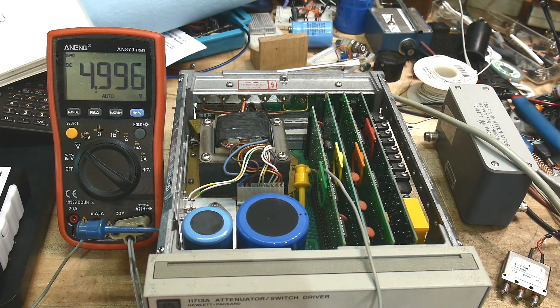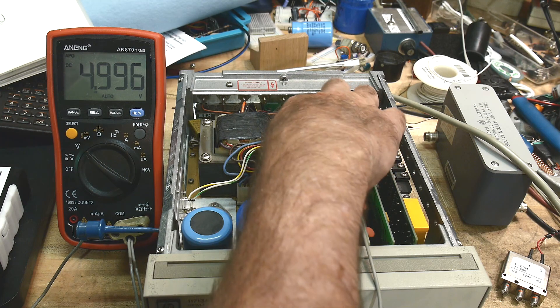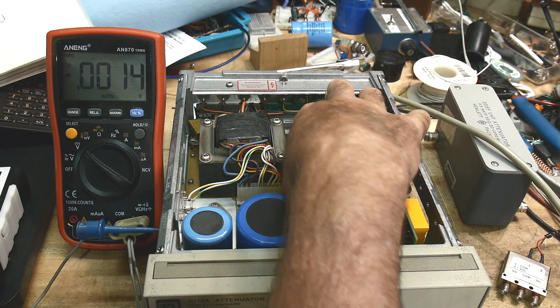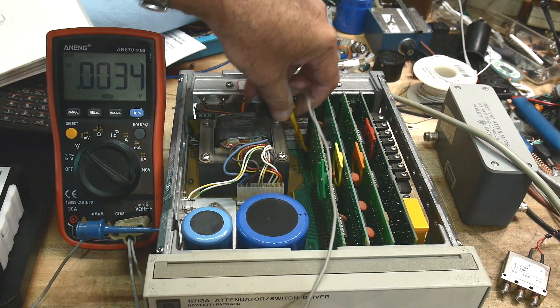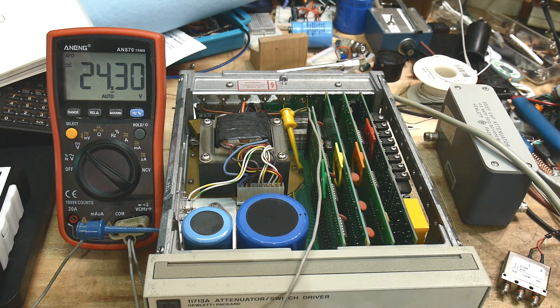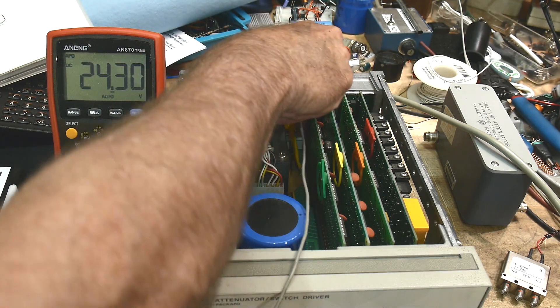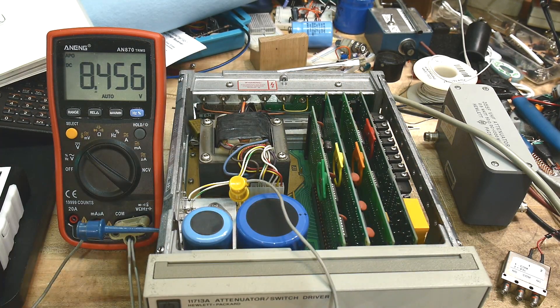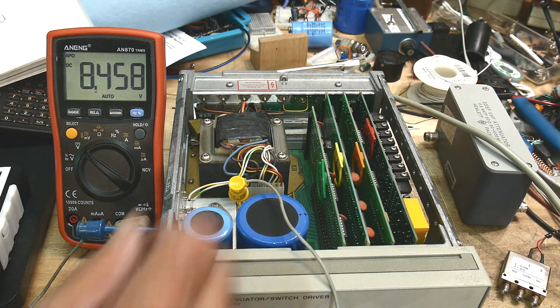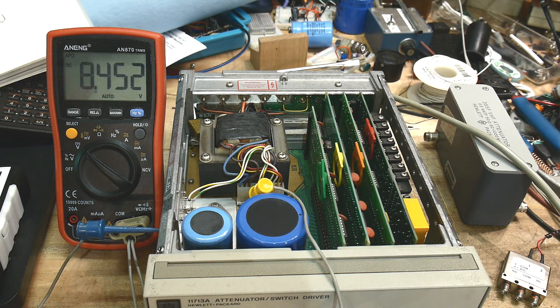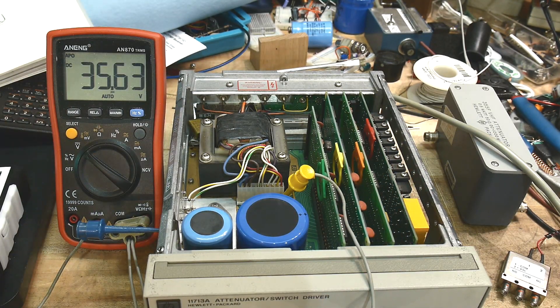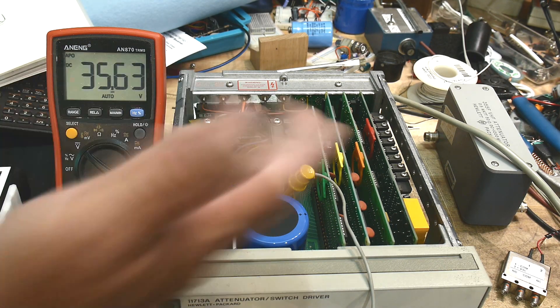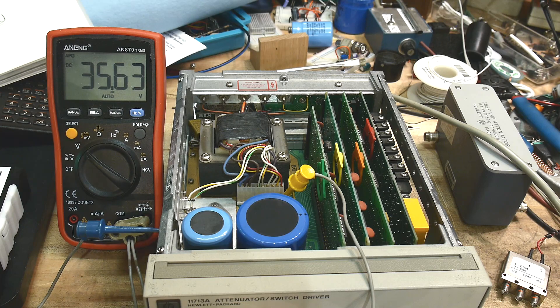I have the voltmeter out here and we're measuring the five volt supply and it's giving us 4.996, looks very nice. And there's another test point over here, 24.3. So those are the two supplies and let's take a look at the unregulated voltages. The unregulated voltage on the five volt supply is 8.4 volts. That's good, you need about eight volts. There's about two volt compliance on the 7805, so you need at least two volts more than the five volts. And then the compliance voltage on the 24 is 35 volts. So quite a bit of compliance there. That might droop a bit when you start pulling current, but it starts out at 35 volts. So that all sounds great.